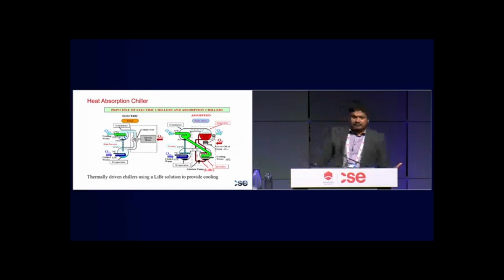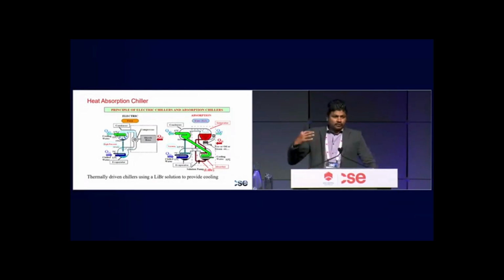For the heat absorption chiller, think of a conventional electric AC unit where the electric motor is - you can substitute that with a lithium bromide solution system. Because of lithium bromide's affinity towards water and the different vaporizations, these principles allow the lithium bromide system to run this chiller. That's basically the theory behind heat absorption chillers.